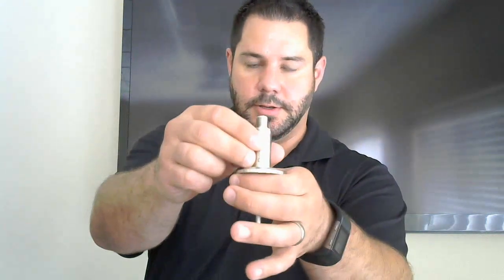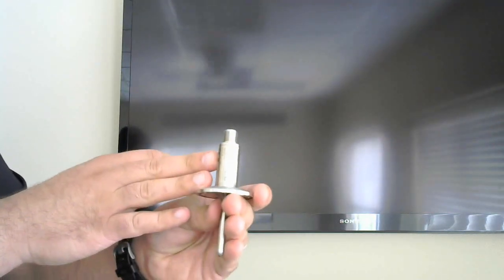So we asked them, and they said, if you could give us something smaller, more compact, and easier to handle when calibrating it. So what we came up with first is this design. This is just a tri-clamp RTD. That's the whole RTD right there, comes out of the top with just a 4 to 20.